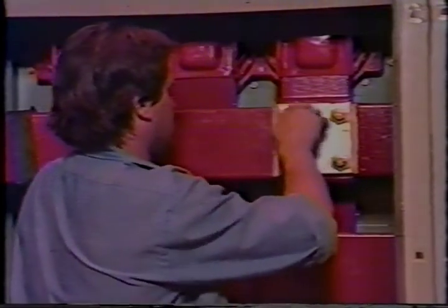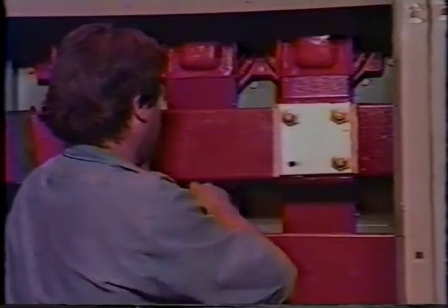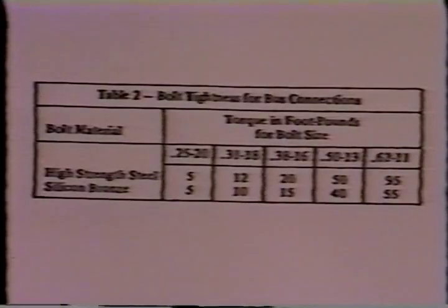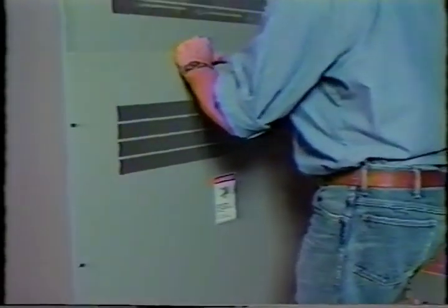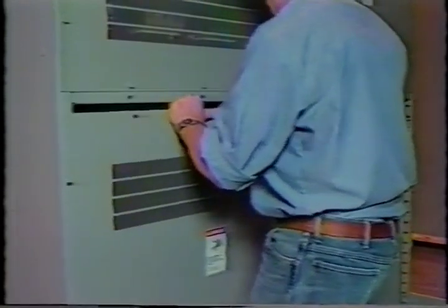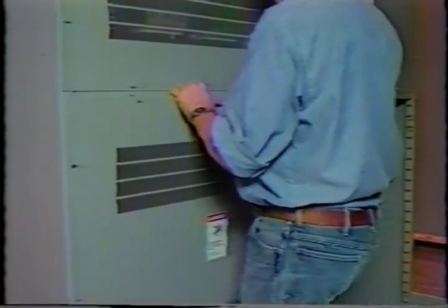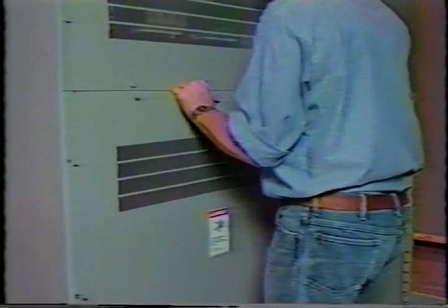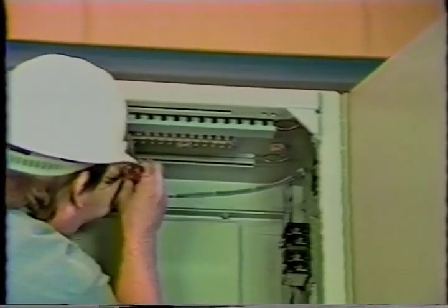Tighten the bolts in the splice plates to the torque values shown in Table 2 of the switchgear instruction book. Replace the metal barriers and any other parts that may have been removed to give access to the bus compartments. Connect the wiring which was disconnected at the factory for shipping. The wiring is labeled.